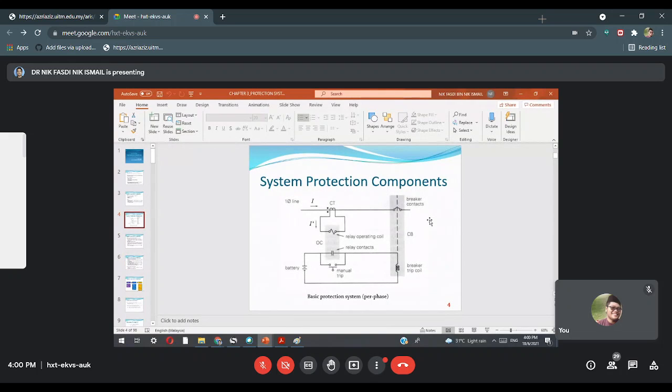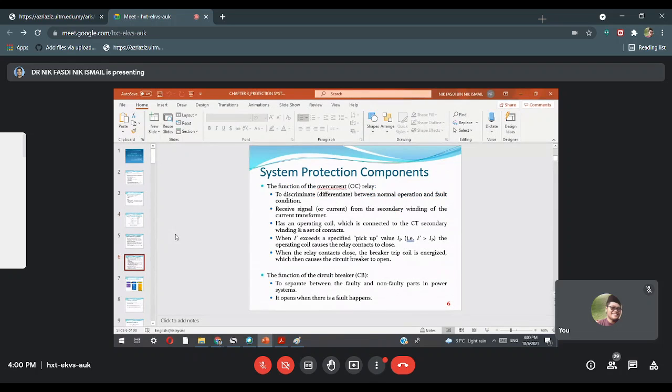Macam case tadi lah. Kalau you kat rumah cakap tadi, you manually open. We close dan you buat manually. Tapi ada juga dalam protection ni kita ada manual trip yang untuk let's say mungkin ada maintenance engineer yang ada standby, tiba-tiba dia ada fault tapi current transformer problem, tak working, so what happen, dia kena manual trip, boleh juga. So this is two way how to control, how to do the protection in the power system network.